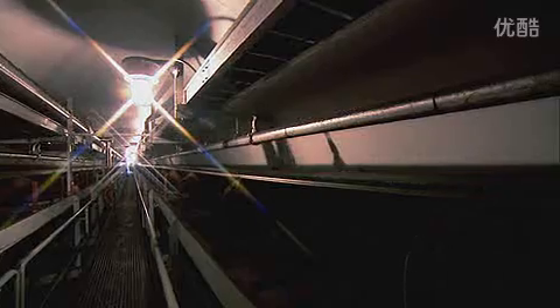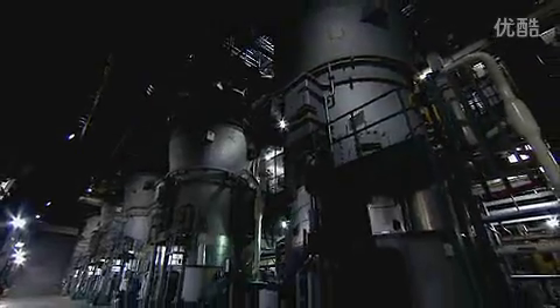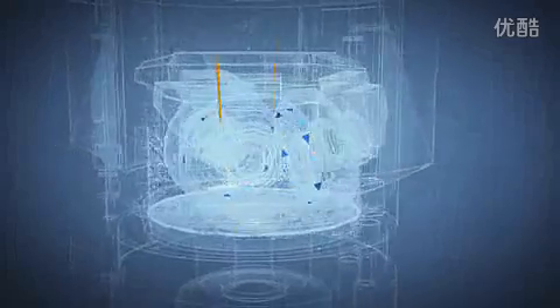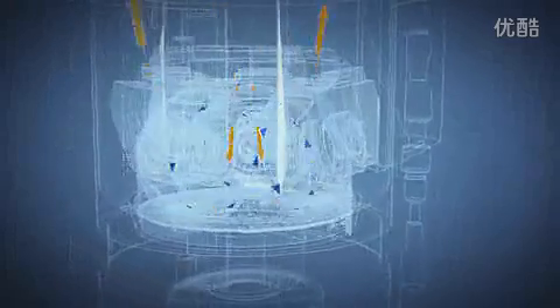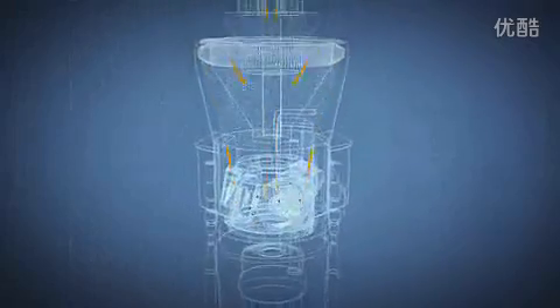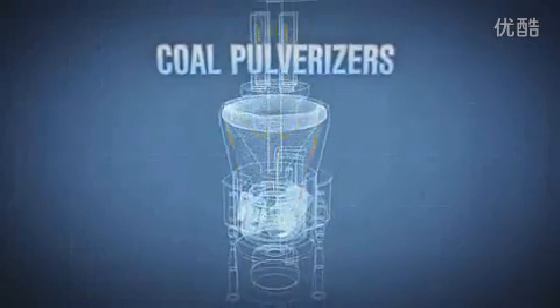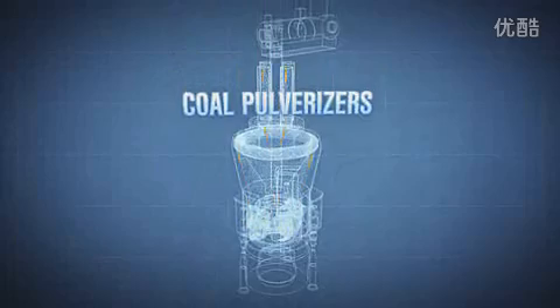Once the conveyor belts bring the coal into the plant, it must be ground down in order to be burned. The coal pulverizers or mills. Through gravitational force, coal feeds down the center of one of 6 pulverizers, landing on a table. On the table, 3 large, strong steel wheels grind the once rock-like coal into talcum powder-sized particles. A primary air fan blows the pulverized coal up and out of the pulverizer. Its destination, the boiler.